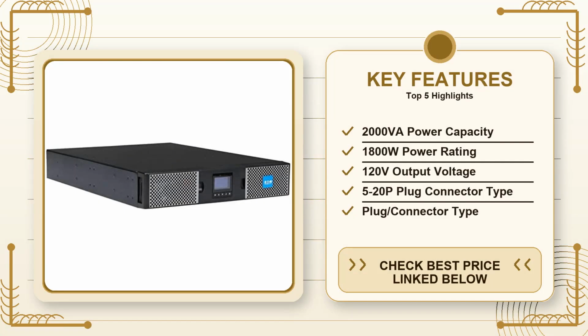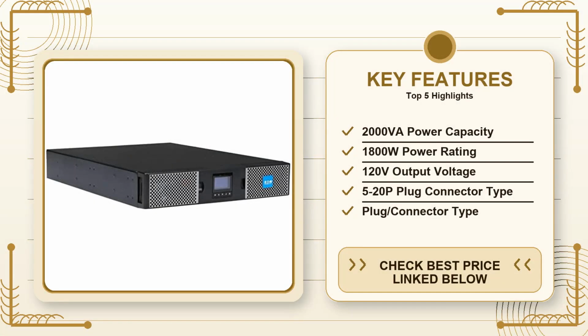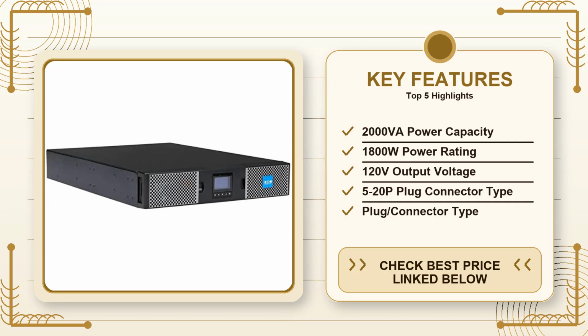One feature that often gets overlooked until you need it is the built-in LCD interface. The display shows input voltage, load percentage, battery charge, and estimated runtime. During a simulated power event, the LCD updated in real time, which helped the operator understand exactly how much headroom remained. It also has a programmable alarm that can trigger an external notification system, useful if you have a small server room where you need to be alerted before the UPS shuts down. That level of visibility is something you don't see on lower-priced standby models.